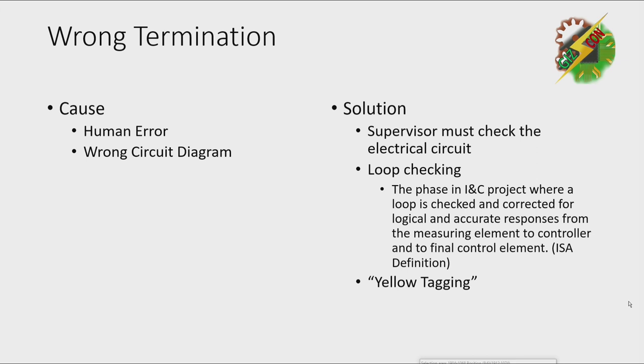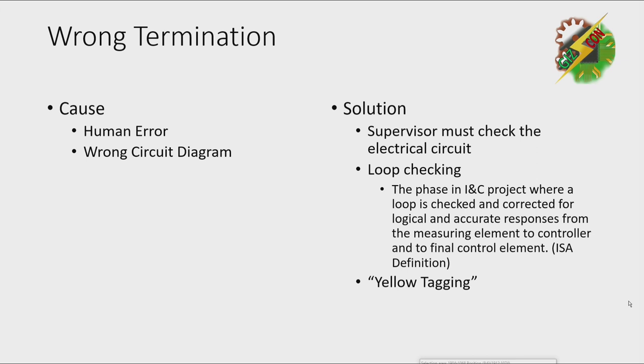Next thing here is by applying a loop check. When we say loop checking, it is the phase in instrumentation and control project where a loop is checked and corrected for logical and accurate responses from measuring element to controller and to final control element. This is an ISA definition.